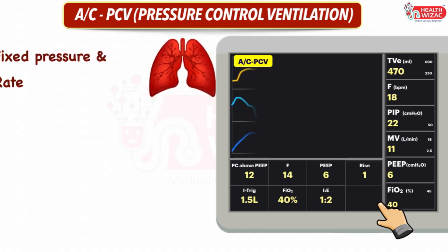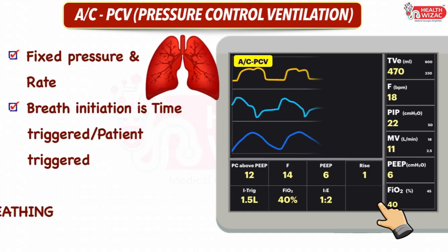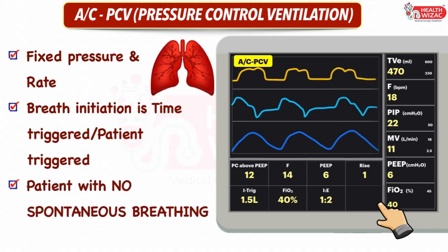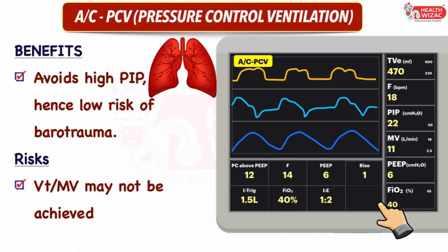In this mode, the ventilator delivers breath at a set pressure and set rate. Breath initiation is time-triggered in control mode and patient-triggered in assist mode. It should be used when the patient has no spontaneous breathing or should be sedated and paralyzed. Advantages include avoiding high peak inspiratory pressure, hence lowering the risk of barotrauma, whereas disadvantages include non-delivery of set tidal volume and minute ventilation.